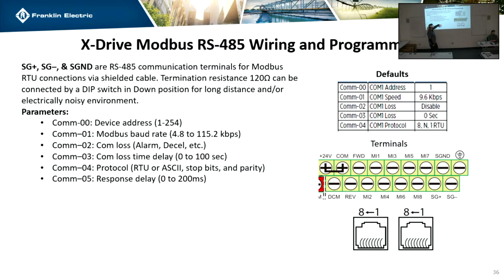There's the defaults. Really the only thing that would change is your 8N1 RTU. This is just the stop bits and the parity stuff. This is pretty standard, most setups use this, and if it's not that, they know that they need to go in and change it. And then comm speed, again, 9.6 is pretty standard, but they'll be all over the place depending on the different building or system or whatever they're doing.